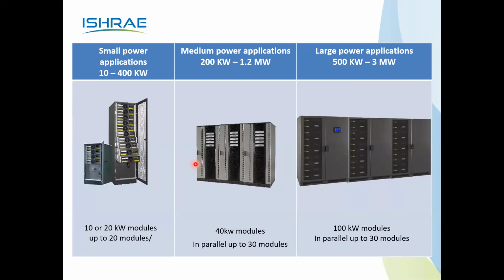For example, the current load is only 100 kilowatt, and the future load is going to be 400 kilowatt. The client can choose the 400 kilowatt frame, and inside the frame, depending on the load requirement, 100 or 200, they can buy particular modules. In that case, energy saving is huge. Instead of 400 kilowatt, the client is using only 200 kilowatt, so at 50% load the efficiency will be very poor. So it is all in our hands how to manage the efficiency. Any electronic component gives better efficiency only if the load is at least 75%. Here the UPS capacity is in our control: what rating they need to buy, what frame size is required.